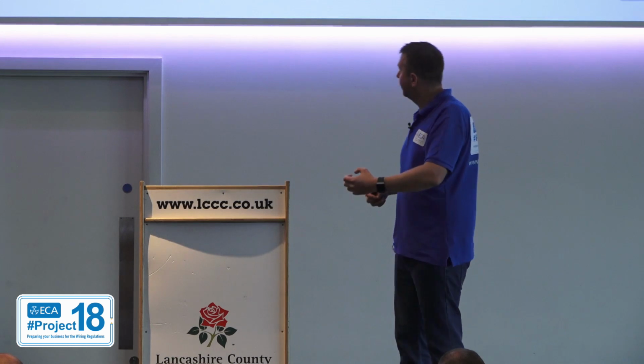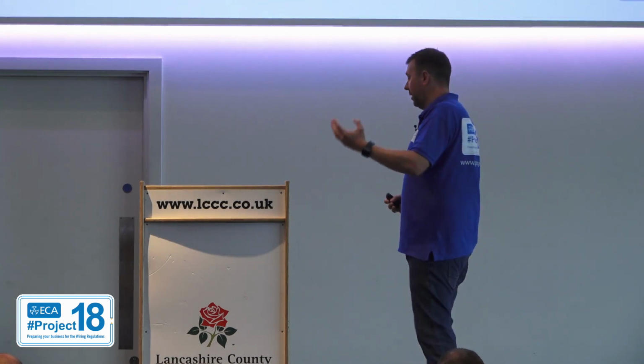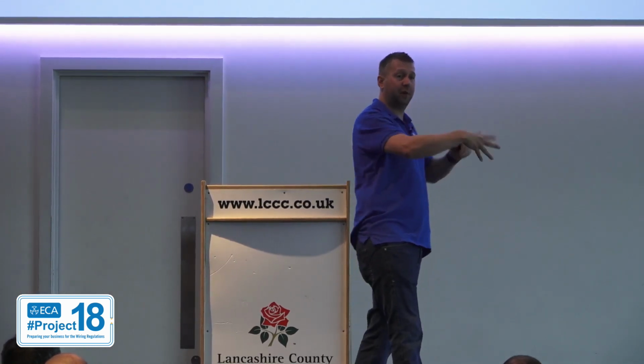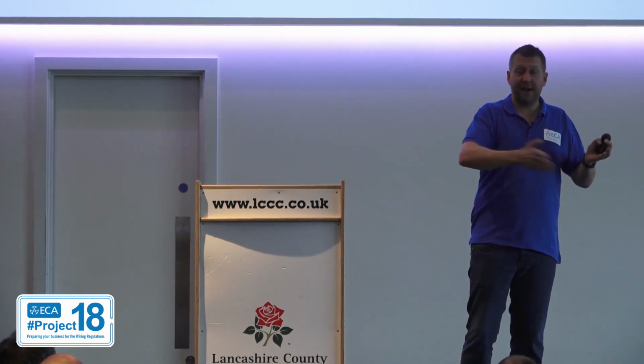I've seen a couple of drafts of it already. It's really good. It's really useful, and it's very, very practitioner-led. It is not overly scientific. It is about how to fit them, where to fit them, what to do. Generally, it's not actually that difficult. Type 1 at origin, Type 2 at sub-boards, and Type 3 further about. And even if you just use all the same manufacturer, you will effectively get selectivity. That's pretty much it. We've put down a lot of information, and it will be coming out shortly to you guys for free.